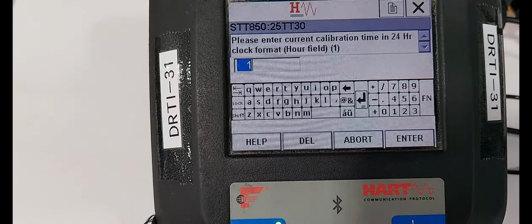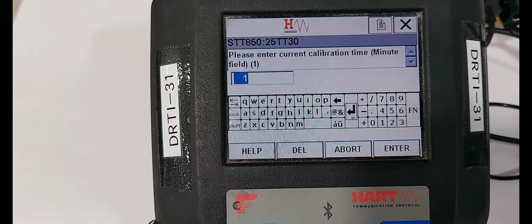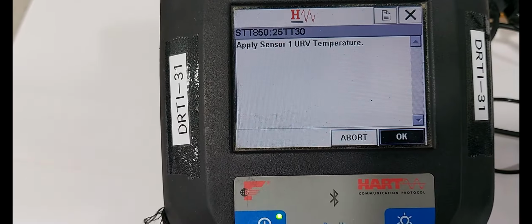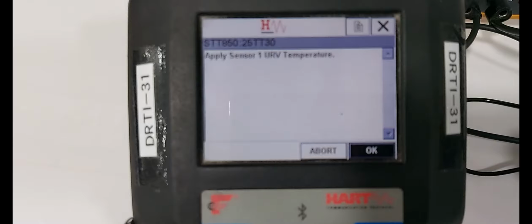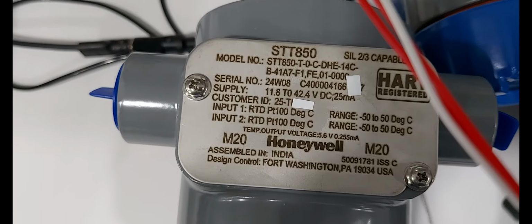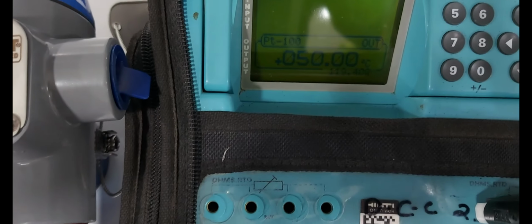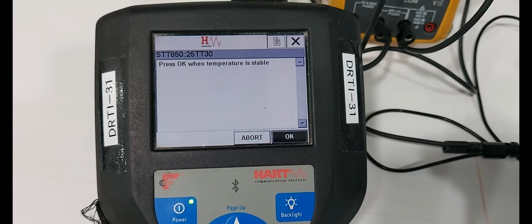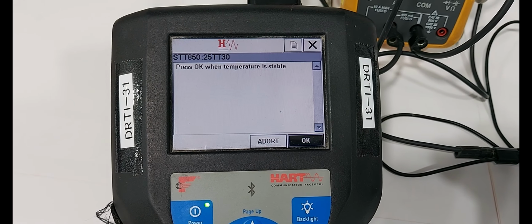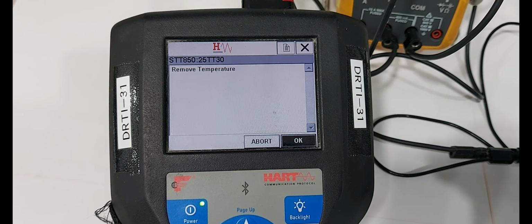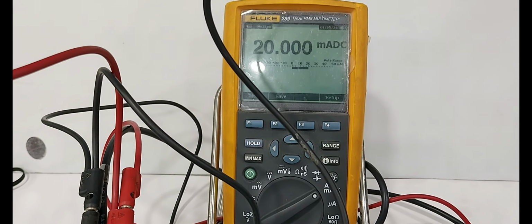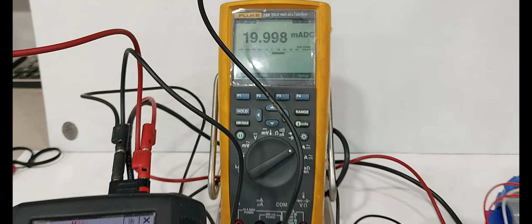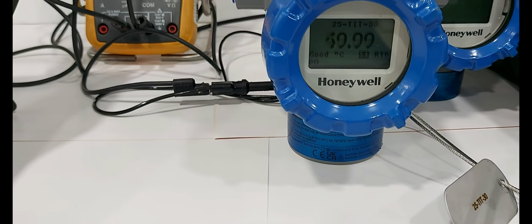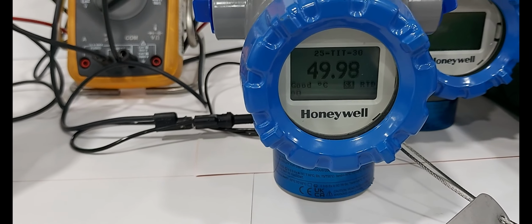Date, timer. Okay. Apply the URV temperature. URV temperature is 50 degrees. We have already simulated the 50 degrees. Then press OK. Press OK. The temperature is stable. Now the reference output is showing 19.998 milliamps DC. The transmitter display is showing 49.98 degrees. Then press OK.